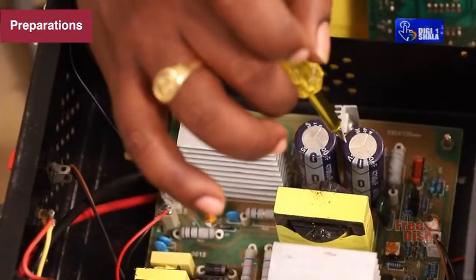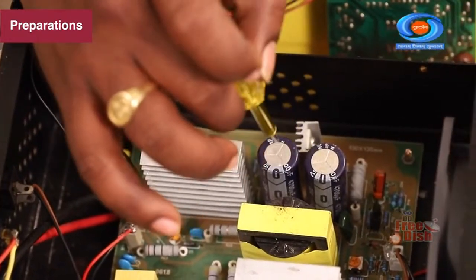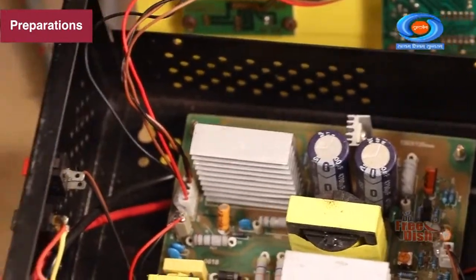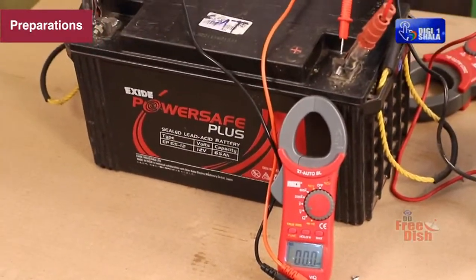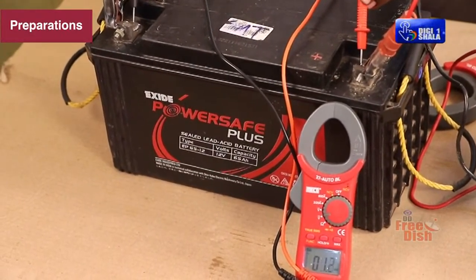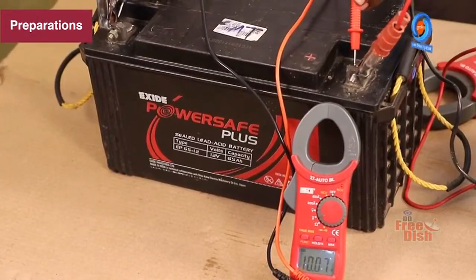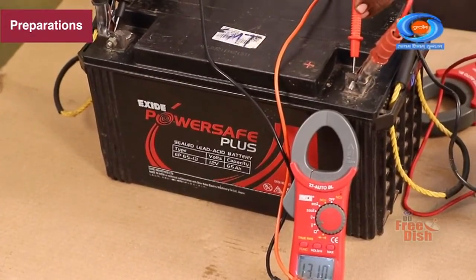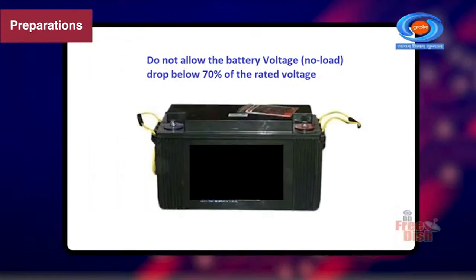And if the voltage is present at relay terminal, we can conclude that the auto cutoff is okay. Check the conditions of the battery. Fully charged battery will show DC voltage at no load about 20% more than the rated voltage. Remember, do not allow the battery voltage at no load to drop below 70% of the rated voltage. If it is so, then reviving the battery is difficult.